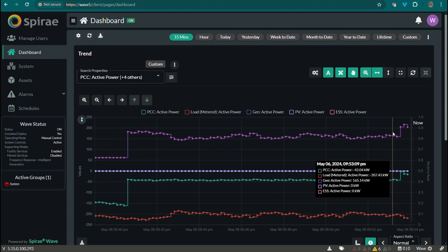I'm running an operation to do a balanced island operation. This performs a planned island outage, synchronizing power flow across the PCC, and once power flow reaches a limited level, it opens the PCC breaker to island the system. In the trend, the green line represents our PCC, right around zero, and you can see the grid breaker has opened. Now we're supporting all our critical loads with just the conventional generation. Gen 1 is currently selected as the master asset, the grid-forming asset on the site.